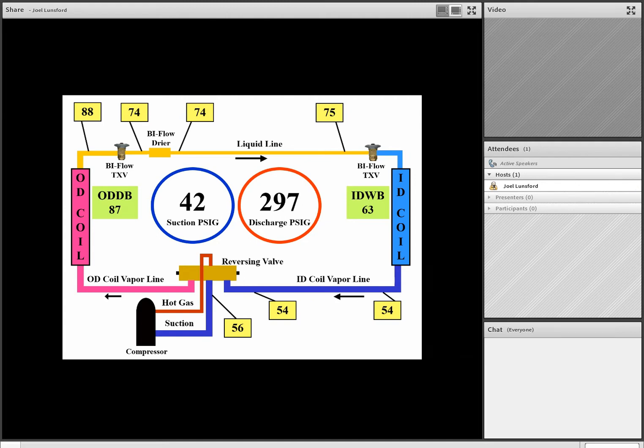That's fine. We also see that we have a liquid line temperature of about 75 to 74 degrees. And we see we have 88 degrees leaving the outdoor coil. So we've activated all of the temperature blocks. Now, team, remember we talked about we should never have any more than a 1 or 2 degree temperature difference across any key component like a biflow filter dryer.